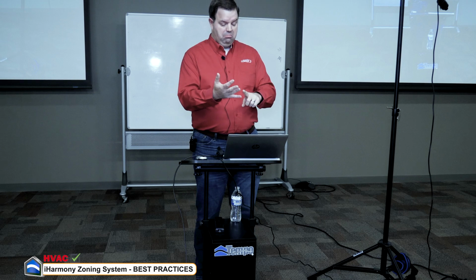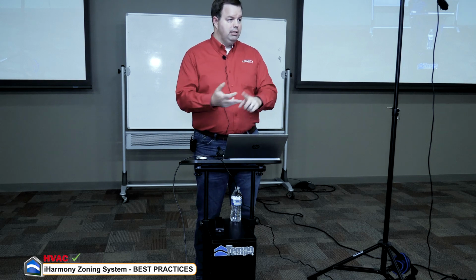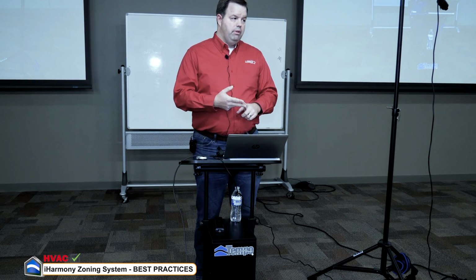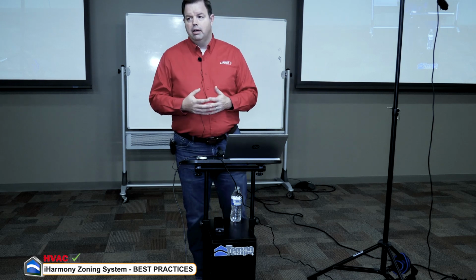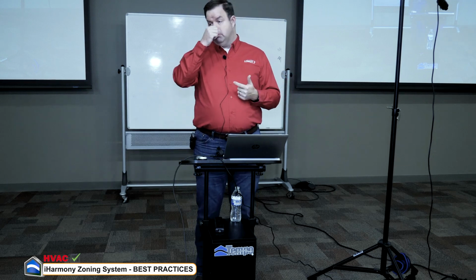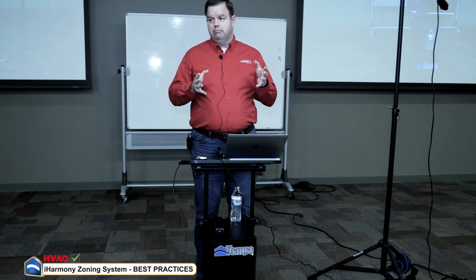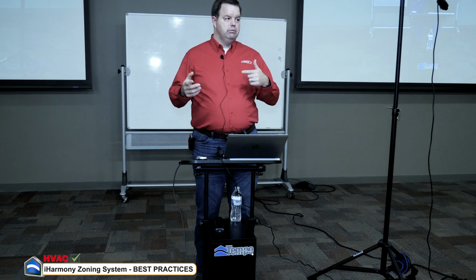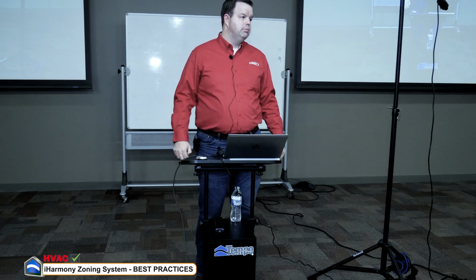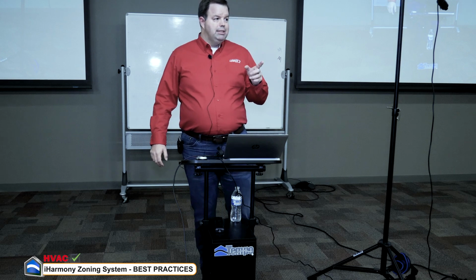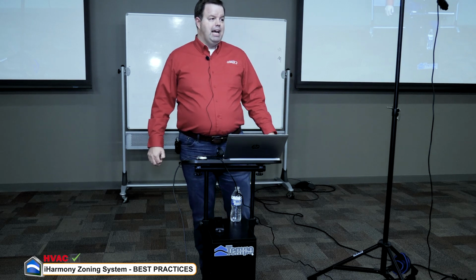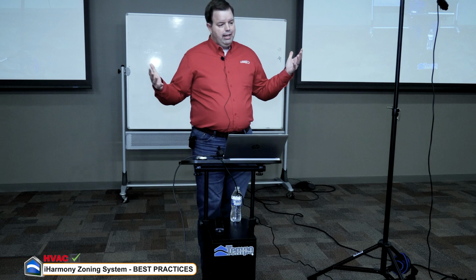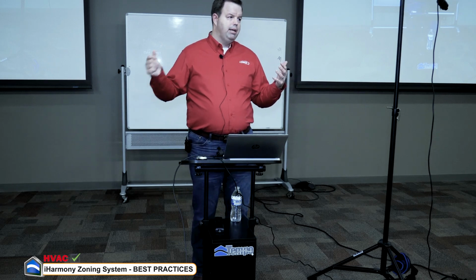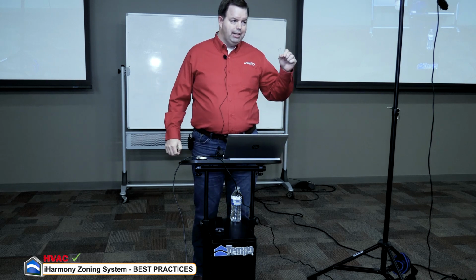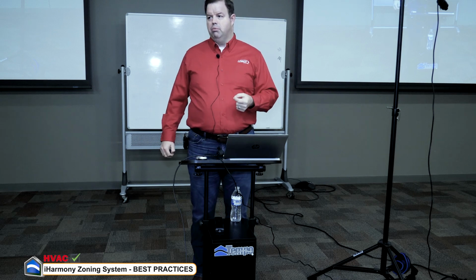And that can be a thermostat, it can be a zone stat, it could be a control board in the unit, a heat pump control board. A lot of these newer boards and components that we're coming out with that are manufactured and spec'd by Lennox, we're starting to put that capability in them. So that's an important step to take, because it's not uncommon, where you do an installation and that first night it may go through a firmware update. So it's important to make sure that they get connected to Wi-Fi and get everything registered properly.